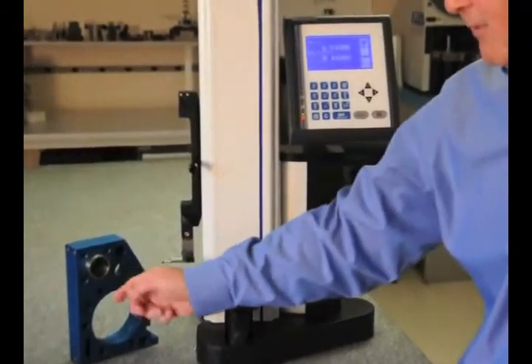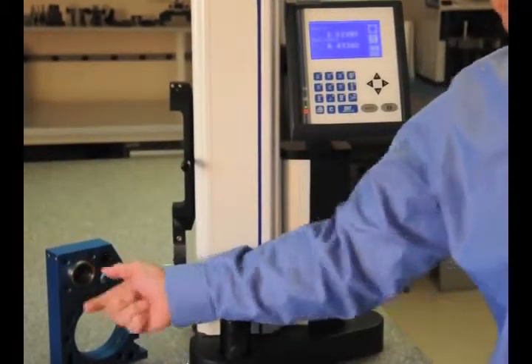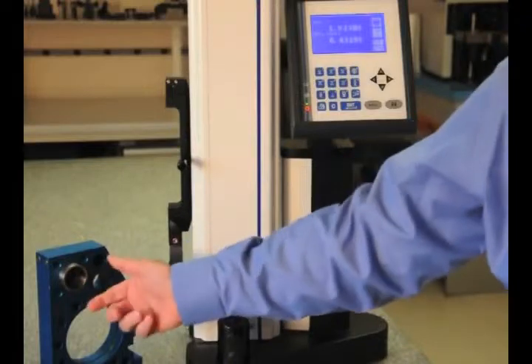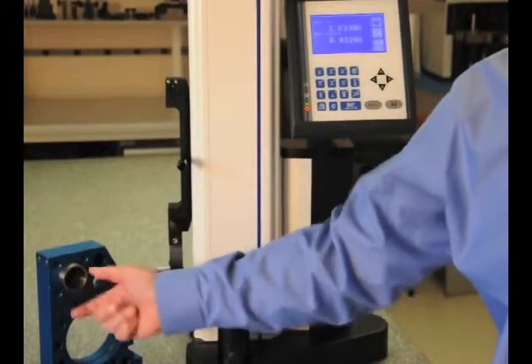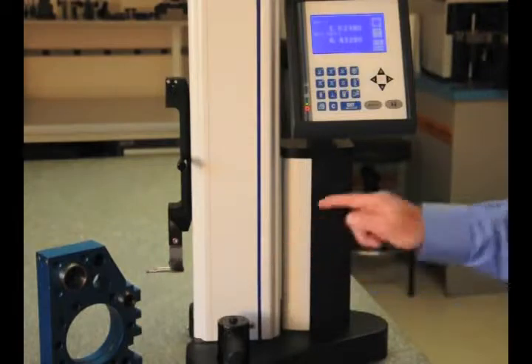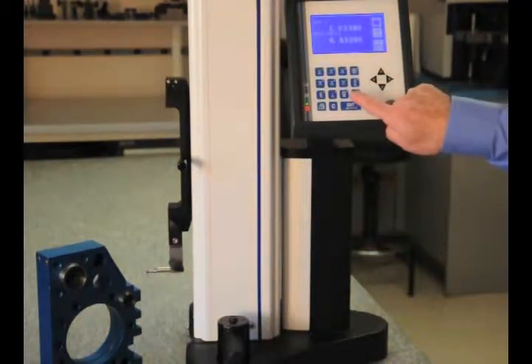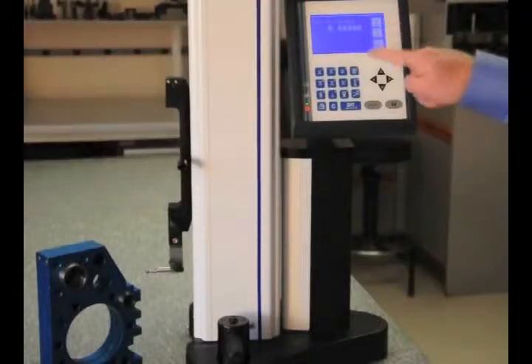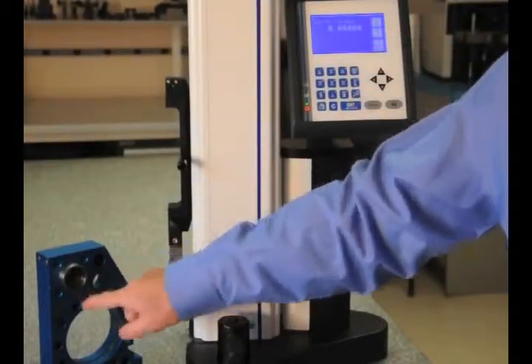Here's our diameter and our center line. Now I'm going to find the diameter of this OD. I'm first going to set zero off of the center line of this ID, because we want to find out the parallelism of this ID to the OD. So I'm going to come over here, and I'm going to hit this reference key. Now it's going to zero out the center line of this ID.